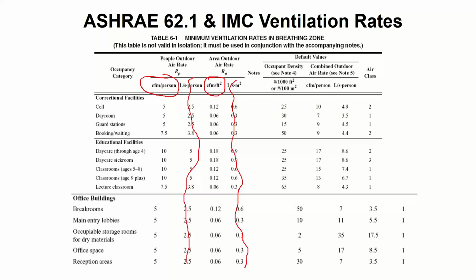It used to be just one combined number of CFM per person, and depending on the vintage of the codes and standards, it was 15 to 20 CFM per person typically. And we used to do it that way. But then in 2004 for ASHRAE, 2009 for the International Code, we separated it into 2 things: CFM per person at a smaller number than we used to have, plus CFM per square foot.